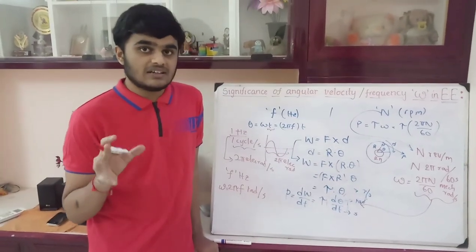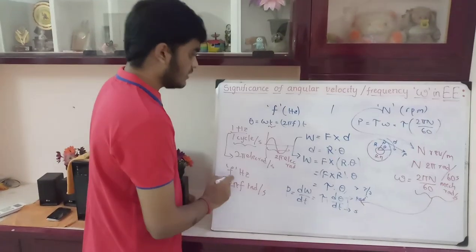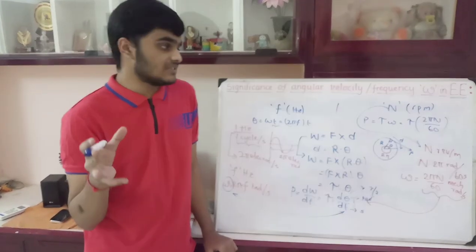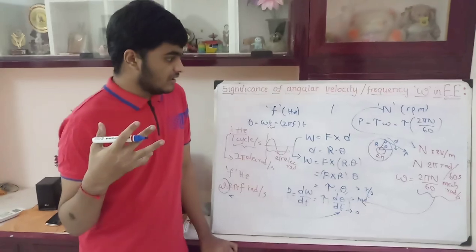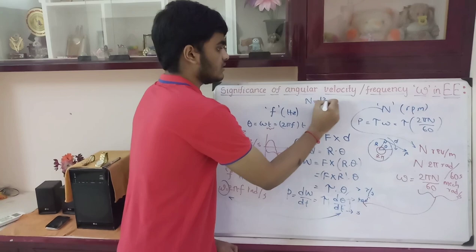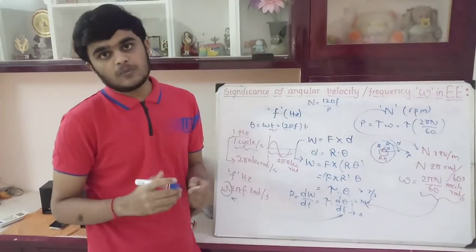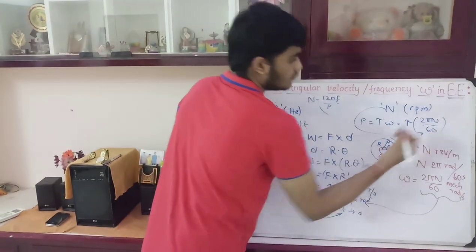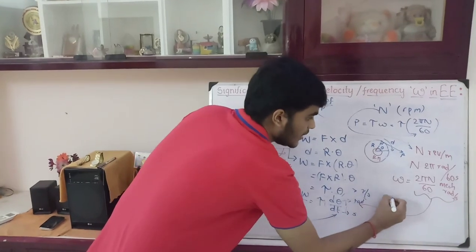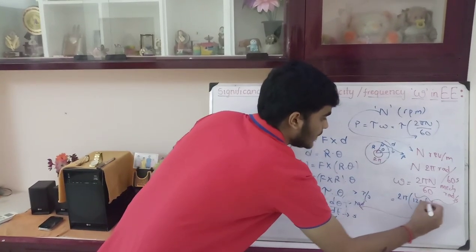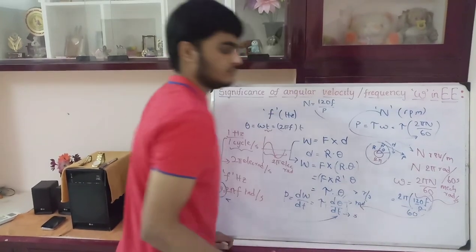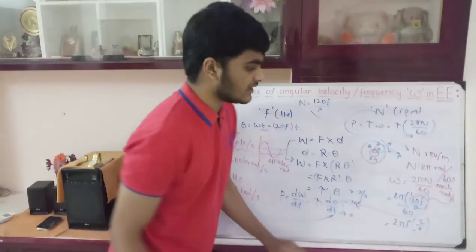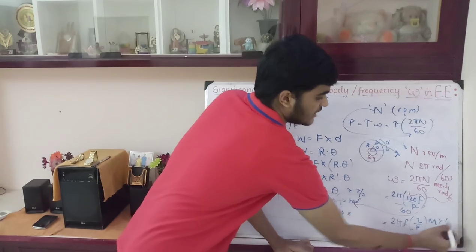Now the important thing to understand is that angular frequency omega and angular velocity omega are both the same — the basic difference is in the units. To understand this, consider the basic equation: the speed of the rotor is N = 120f/p, where p is the number of poles of the rotor. Substituting this N into the equation, we get omega = 2π × (120f/p) / 60, which gives 2πf × (2/p). Here, since it is in mechanical radians, this is also in mechanical radians per second.